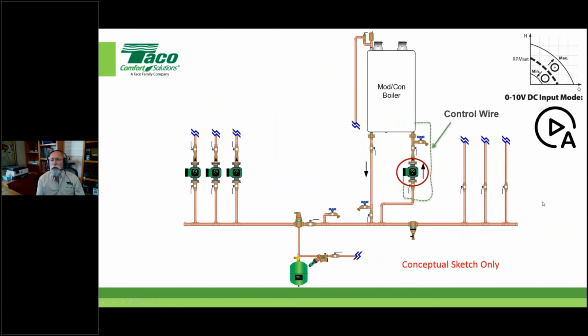But one thing that I mentioned on one of my bullets is the ability for the boiler manufacturer now to have control of the circulator. So what I'm saying is a pump manufacturer like TACO now gives the keys to the boiler manufacturer. Here's the keys, you run me however you see fit. And we're doing that with typically in North America a 0 to 10 volt DC signal down to the circulator. This is not just powering the circulator, it's saying, look, I'm going to power the circulator and I'm going to control its variable speed based on input that I'm receiving from something that's within the boiler manufacturer, right?